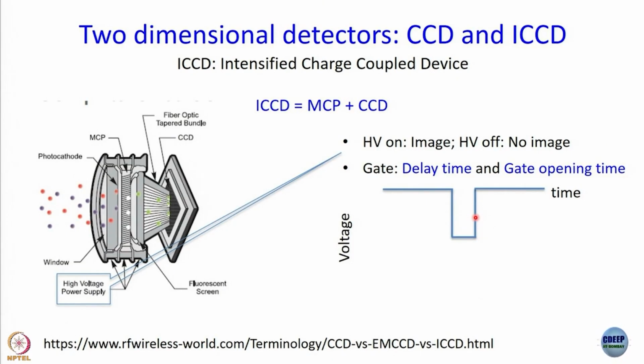In fact, this technology is nothing very new or anything. Even when you want to measure say phosphorescence on a fluorimeter with a pulse source of light, you use this kind of gate delay technique. Okay. The only difference is that there you are giving the high voltage to the photomultiplier tube, here you are giving high voltage to the MCP, which acts here not as the detector as such, but as an intensifier. So, what is crucial here?